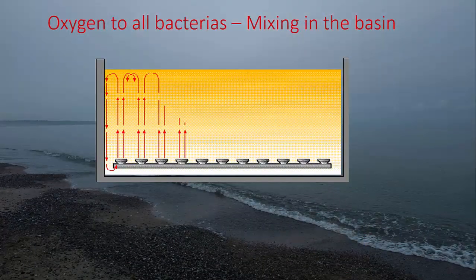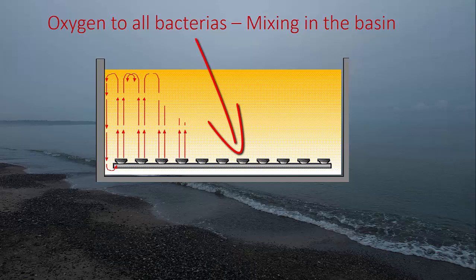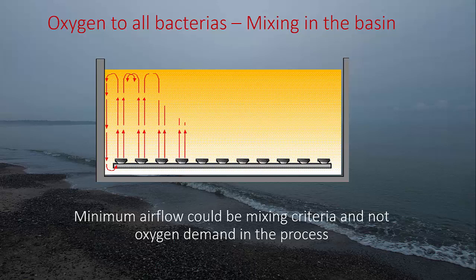Now let's look at the mixing in the basin. You have all the bacteria — all the sludge — that needs to be mixed so that the bacteria get into good contact with all the air bubbles giving them oxygen. In the schematic you can see the aeration system at the bottom, showing how the air circulates and mixes the sludge in the tank for very good mixing. When designing aeration, one thing to consider is that the minimum airflow could be determined by what we call a mixing criteria — because you always have to keep a good mix in the tank. That airflow for mixing could actually be more than the bacteria need for oxygen.